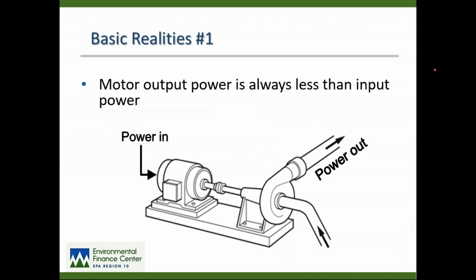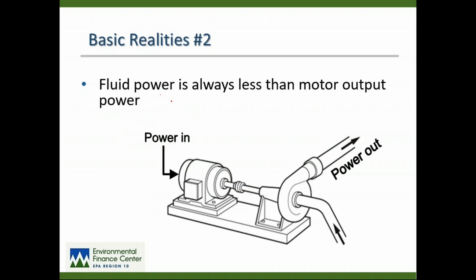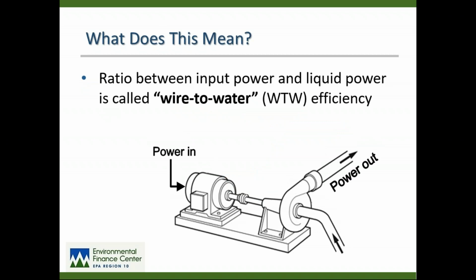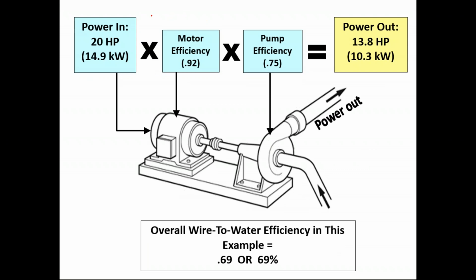Okay, this is a term that you would probably see on any distribution exam anywhere in the country. This is wire-to-water efficiency. Motor output power, which is the power that is developed on the shaft end of a motor, will always be less than motor input power, which is the power that you are purchasing from your energy provider and paying for. That's the first law of physics. That's the first inefficiency, the inefficiency within the motor. Fluid power, which is the energy that is developed on the discharge side of the pump, will always be less than motor output power, which we already explained. The ratio between input power and liquid power is called wire-to-water efficiency. Again, you probably will have a wire-to-water efficiency problem on your distribution, or maybe even a treatment exam, wherever you are in the country.